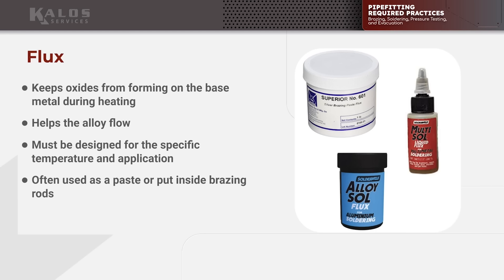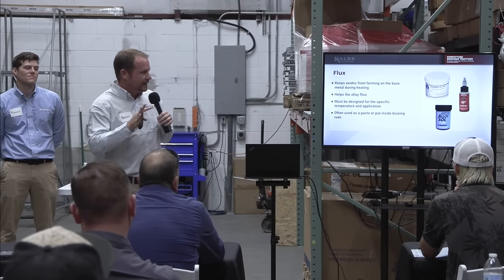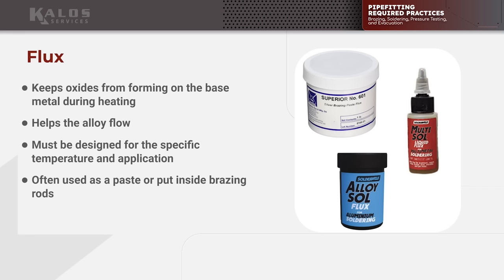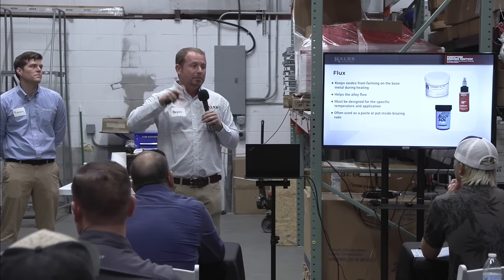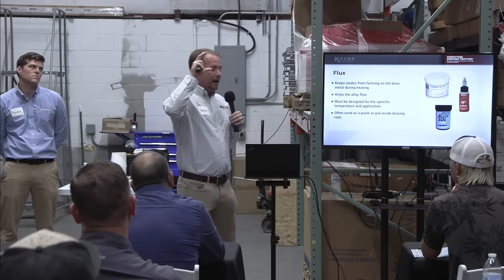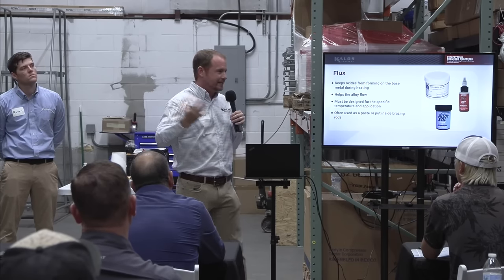When we choose a flux, we choose it because we're working with a dissimilar metal and it needs to be designed for it. There's soldering flux, Alloy Sol, which is an aluminum flux for aluminum alloy, and silver brazing paste flux which works with dissimilar metals. If you're ever working with steel to copper or steel to steel, get a black paste flux — it's a high-temperature paste flux that gives you more room to work with and is less likely to burn.